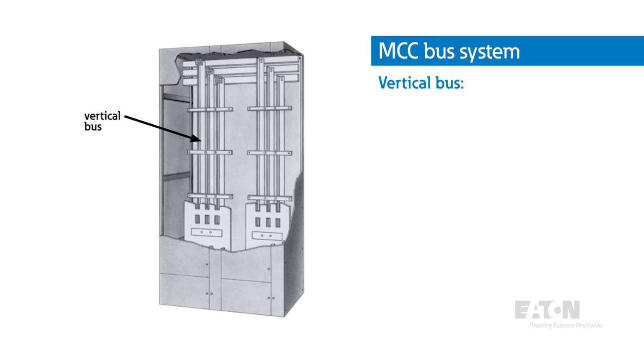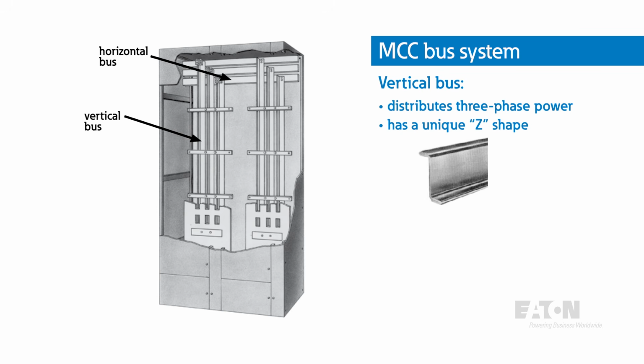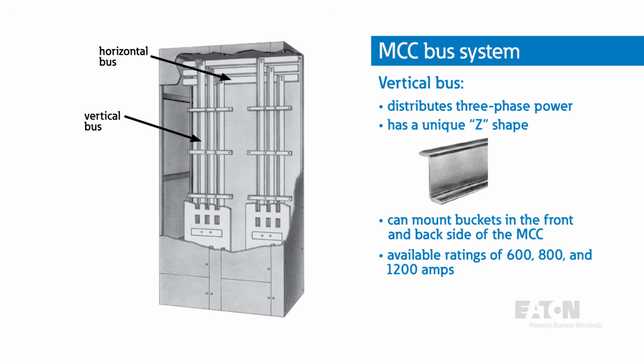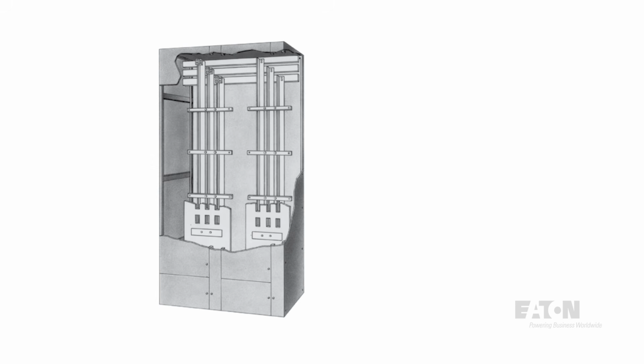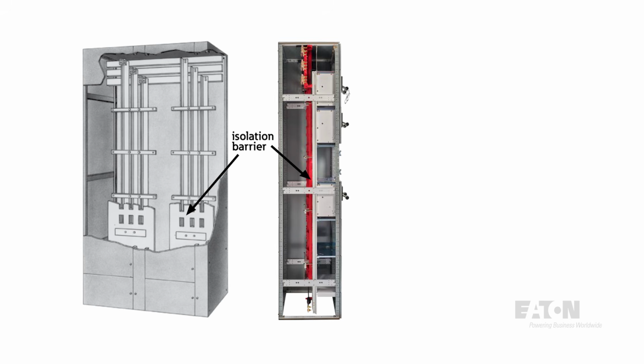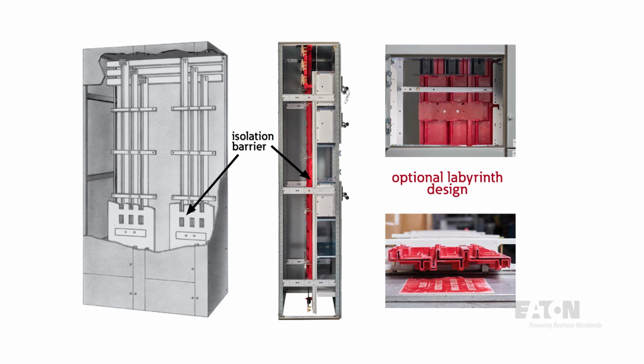The vertical bus distributes three-phase power from the main horizontal bus into the vertical compartments. It has a unique Z shape for added strength and smooth connection, as well as the ability to mount buckets in the front and back side of the MCC. The vertical bus is available in ratings of 600, 800, and 1200 amps and is made of tin-plated copper for durability. The vertical bus compartment is isolated from the unit compartment by a full height barrier. Optional labyrinth design barriers provide protection against phase-to-phase insulation breakdown, and an automatic shutter mechanism prevents exposure to the vertical bus during maintenance.